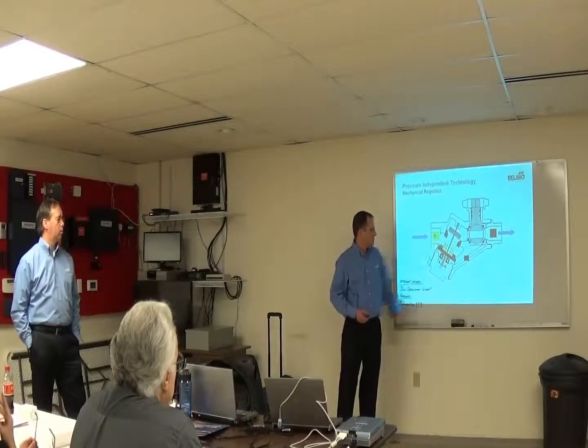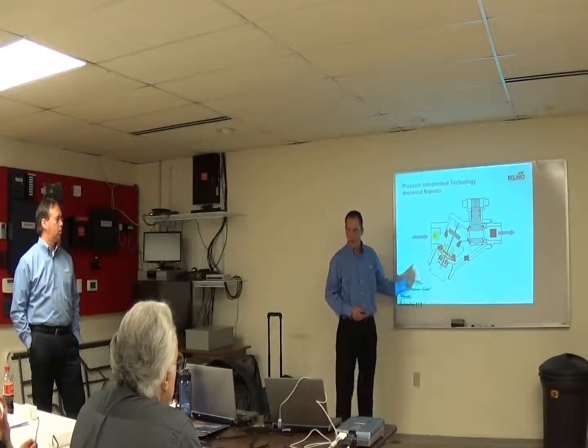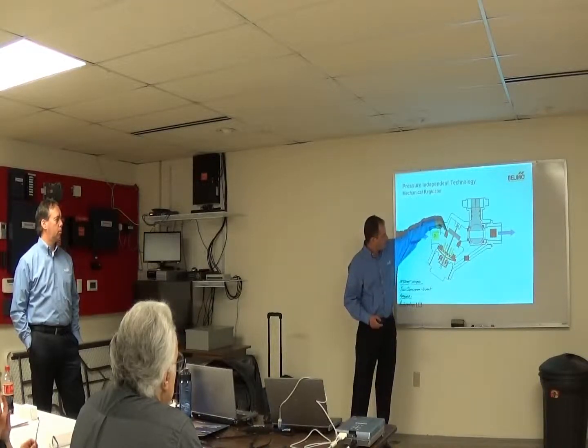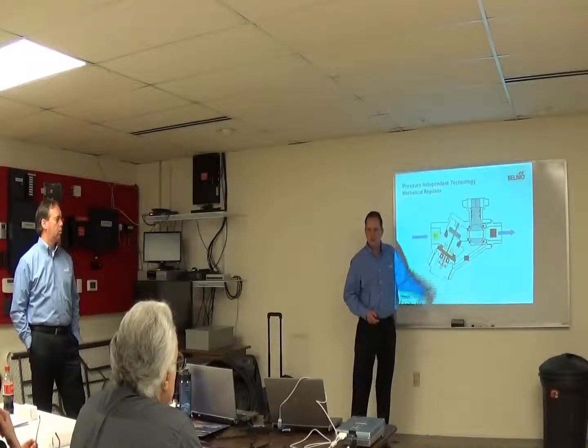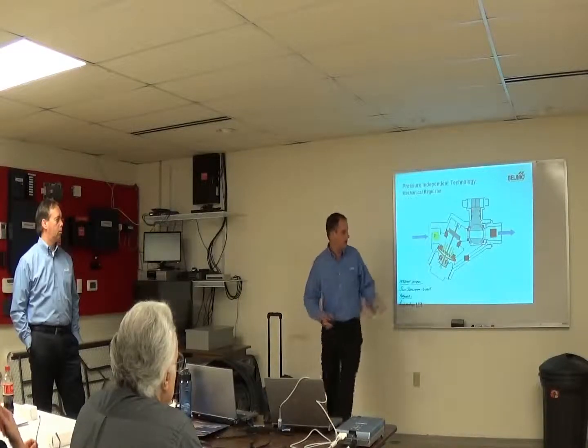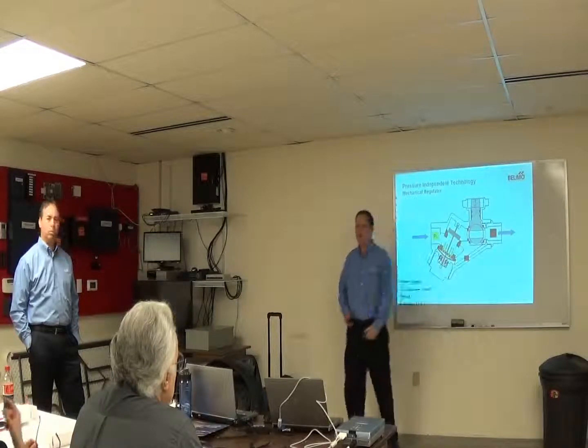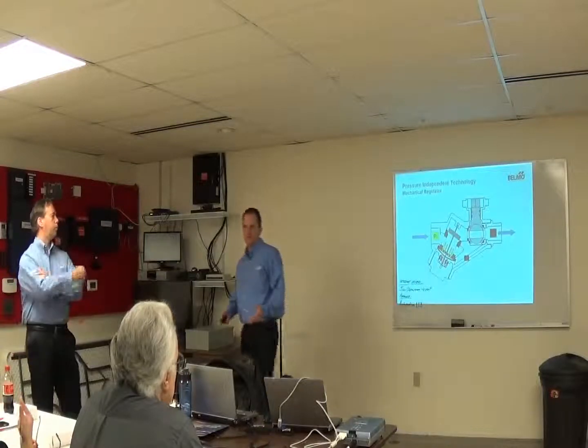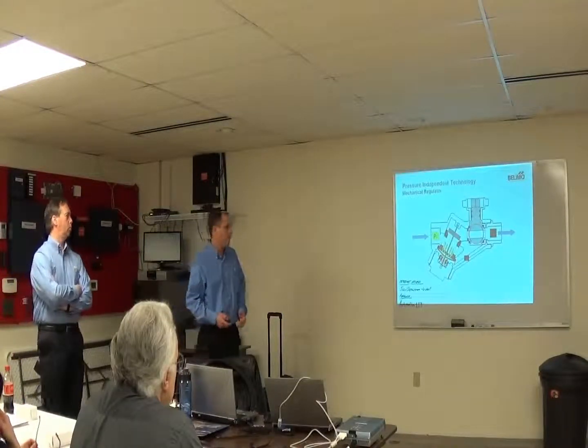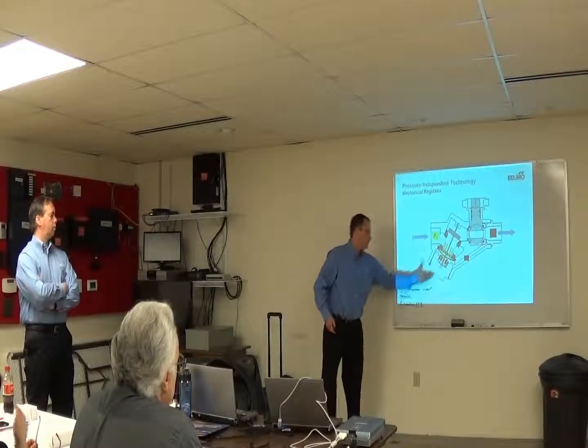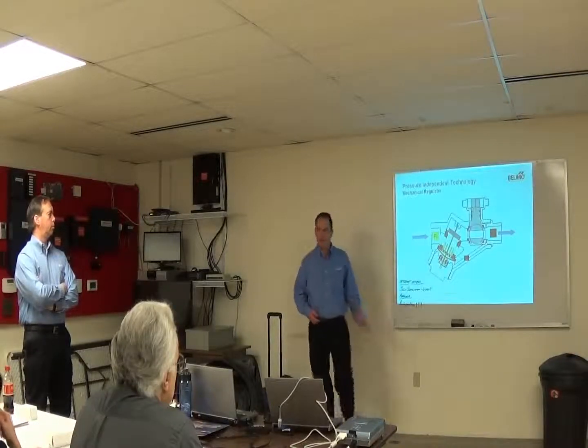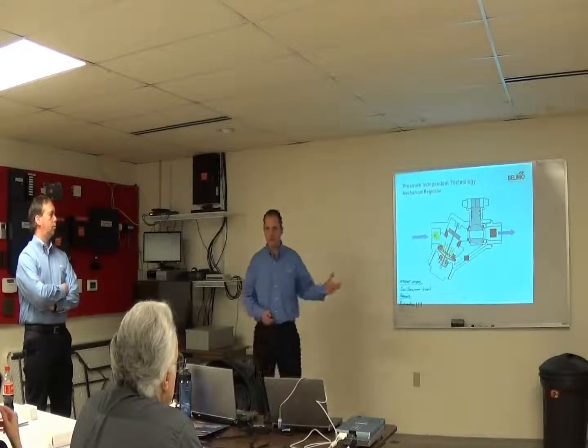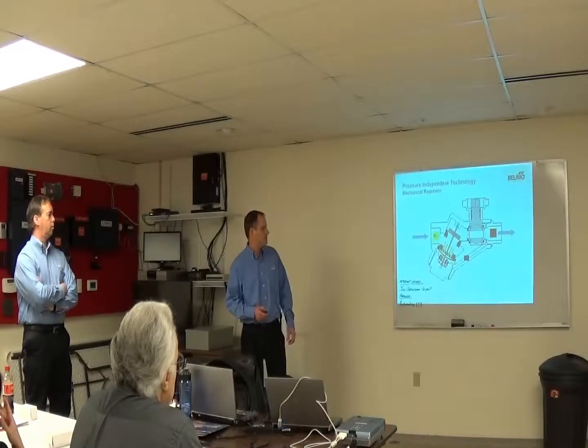And then there's this plunger. As the pressure increases on the upstream, it pushes down, so less water flows through these channels. So it's pretty simple. Basically, we're guaranteeing we've always got that 5 PSI across our ball valve. So this is basically like a pressure regulator. Any excess pressure, it eats it up, absorbs it, and guarantees 5 across that.